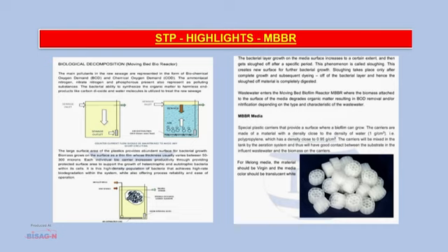Each individual biocarrier increases productivity by providing protected surface area to support the growth of heterotrophic and autotrophic bacteria within the cell. It is the high density population of bacteria that achieves high rate biodegradation within the system, while also offering process reliability and ease of operation.